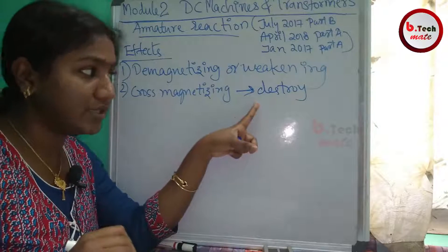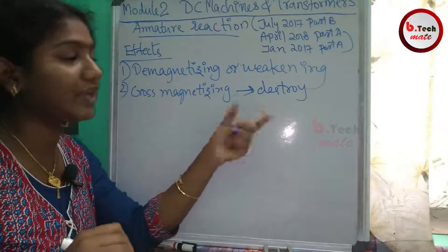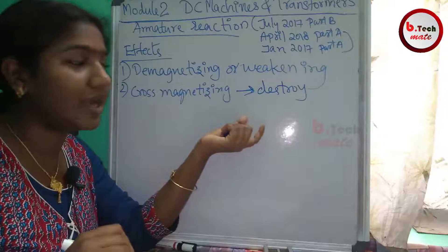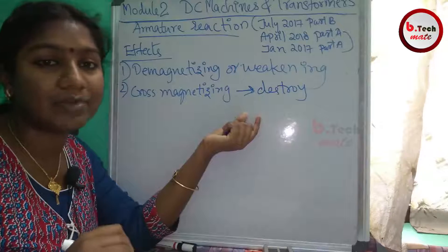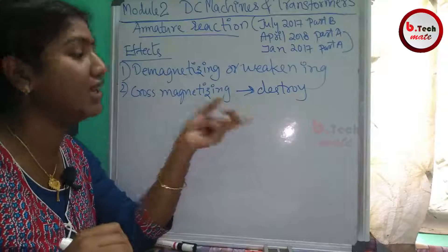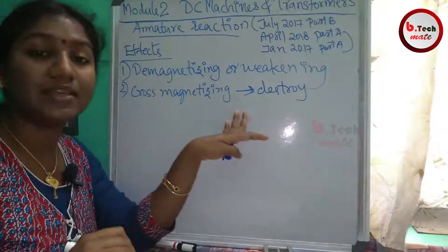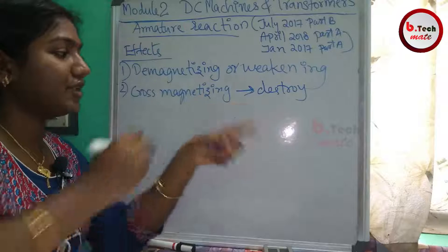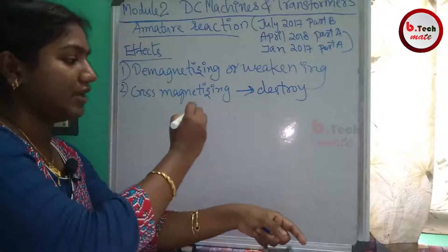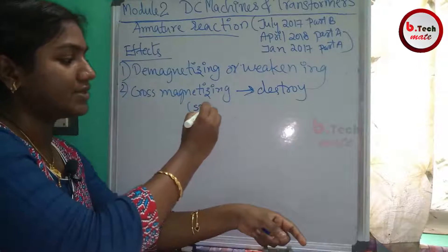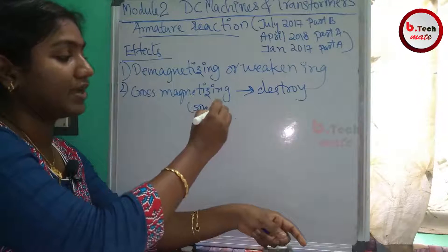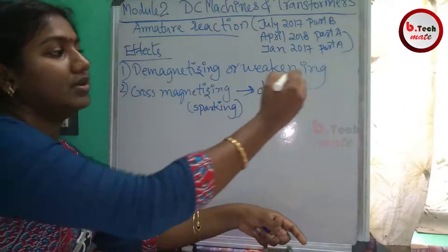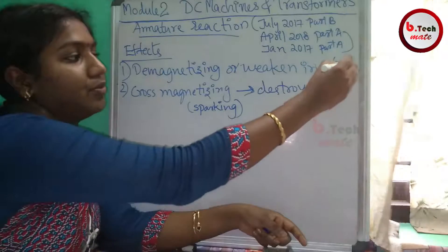The distortion caused by the armature flux leads to sparking at the commutators and brushes. The Cross Magnetizing effect causes sparking, while the Demagnetizing effect reduces the generated EMF (EG).